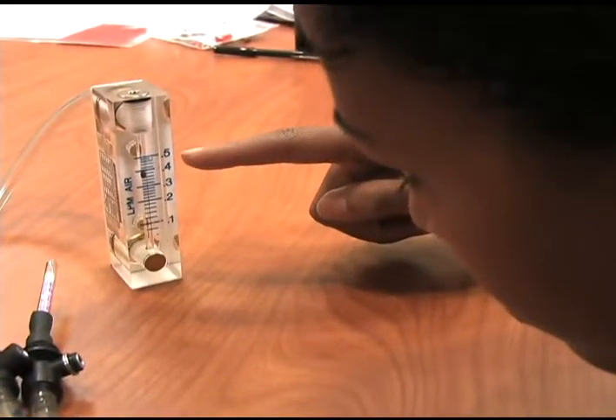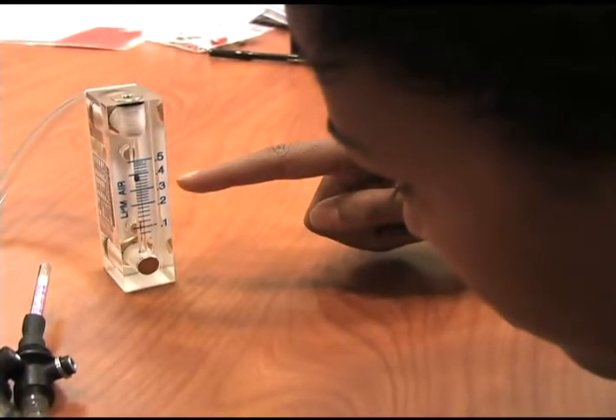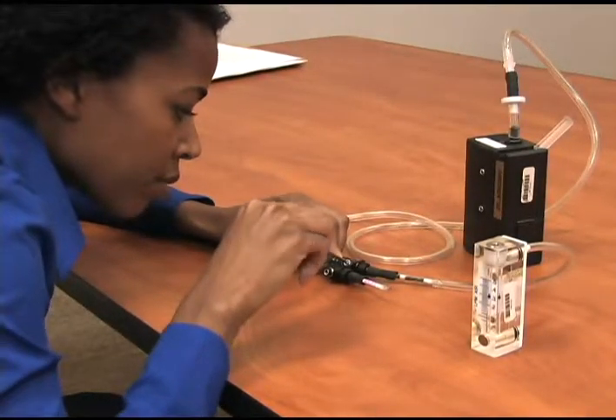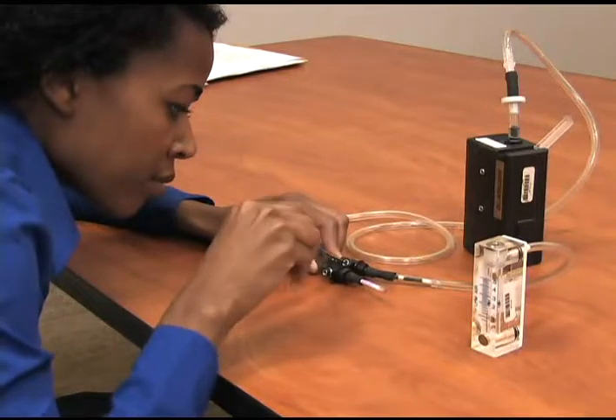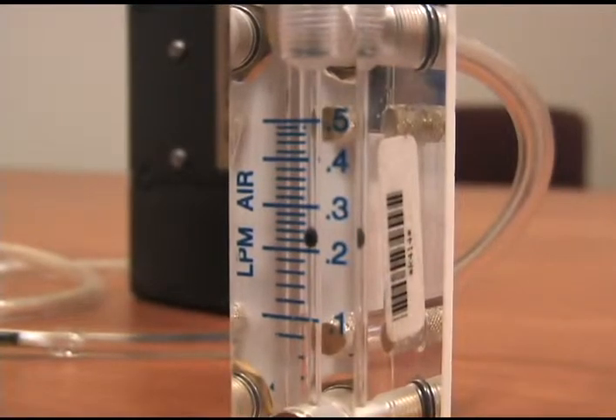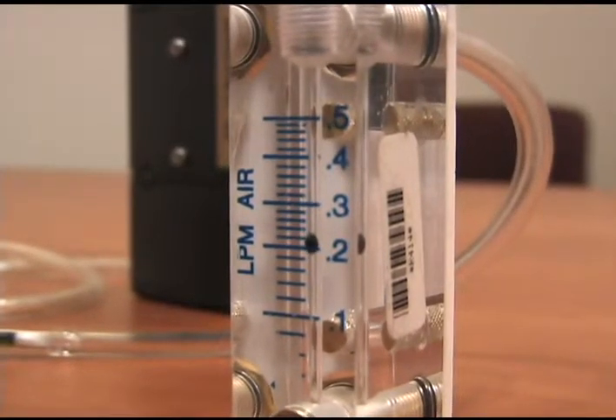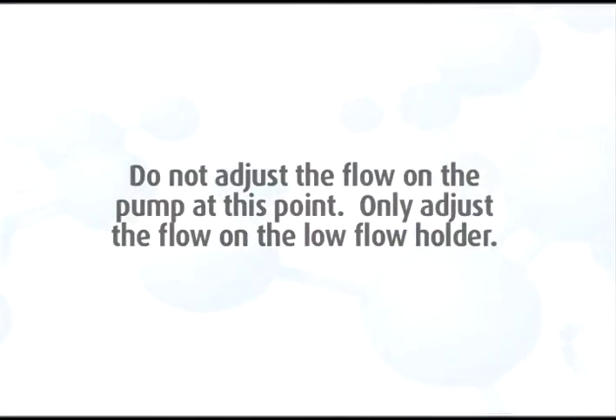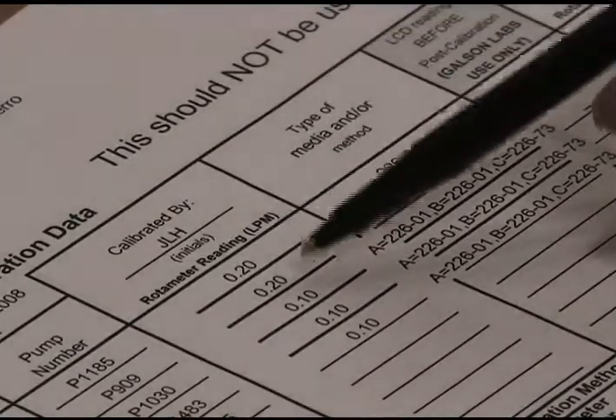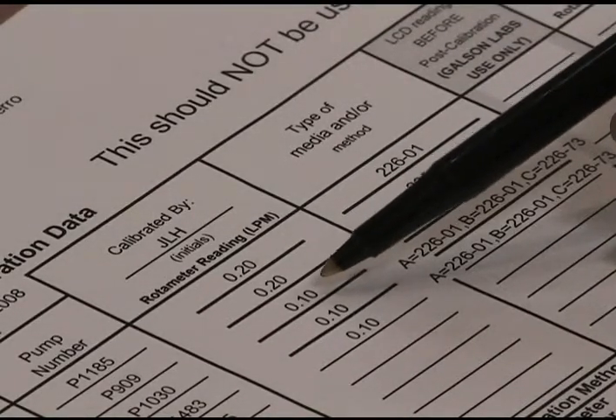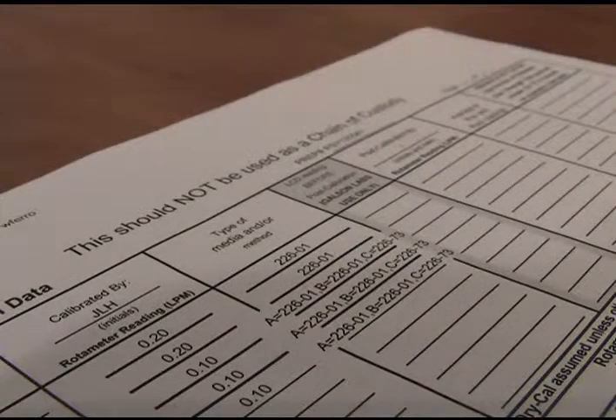With everything sitting on a level flat surface, check the ball float in the rotometer. Adjust the flow rate by turning the flow adjustment screw on the adjustable low flow holder until the rotometer indicates the desired flow. Be sure to take your rotometer reading at eye level and use the center of the float for the value. Do not adjust the flow on the pump at this point. Only adjust the flow on the low flow holder. After you are satisfied with the flow rate, verify the value matches that on the pump calibration data sheet and repeat the previous steps for additional port marked B for dual splitters and B and C for triple splitters. The pump calibration data sheet has separate calibrations for A, B, and C ports, so be sure to record your value with the correct tube sleeve.